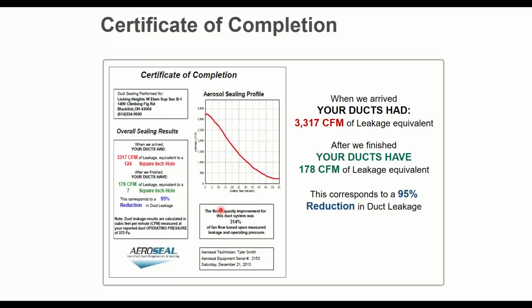So that's going over the course of about 55 minutes it took to seal this duct system down, from an initial leakage rate of 3,300 CFM down to 178 CFM. So that was a 95% reduction in leakage. You're saving 3,000 CFM of duct leakage at this point.